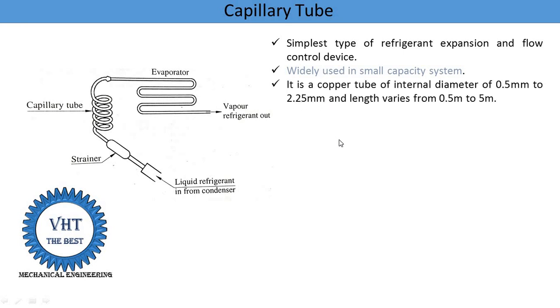The capillary tube has a certain diameter and certain length. It is available in different diameters and lengths. The copper tube has an internal diameter of 0.5 mm to 2.25 mm, and its length varies from 0.5 meters to 5 meters. Diameter is given in mm and length is in meters.